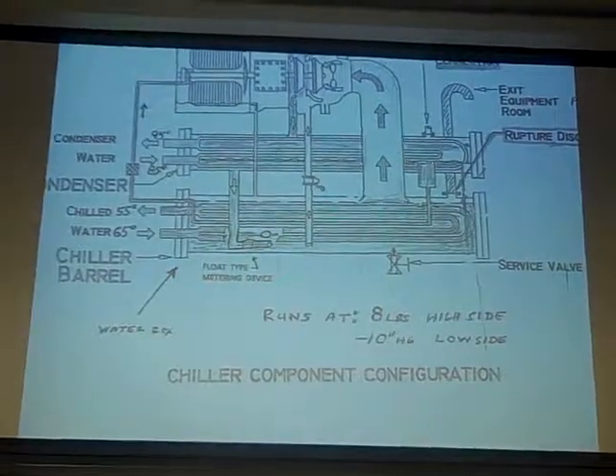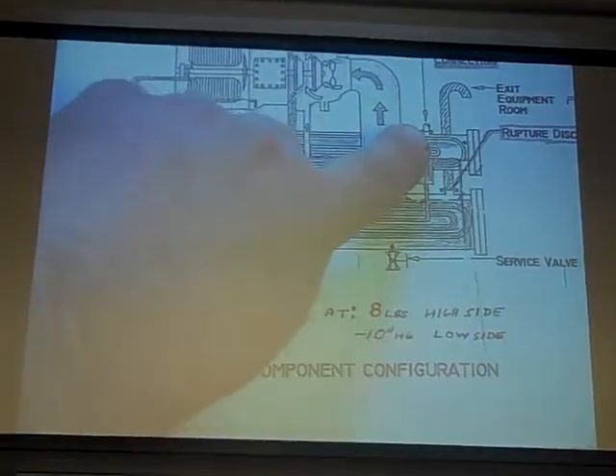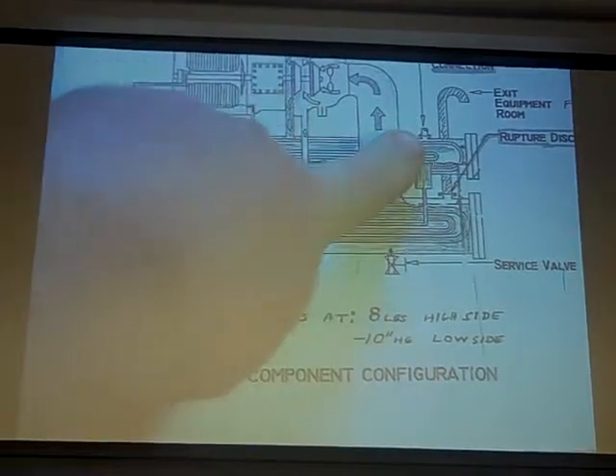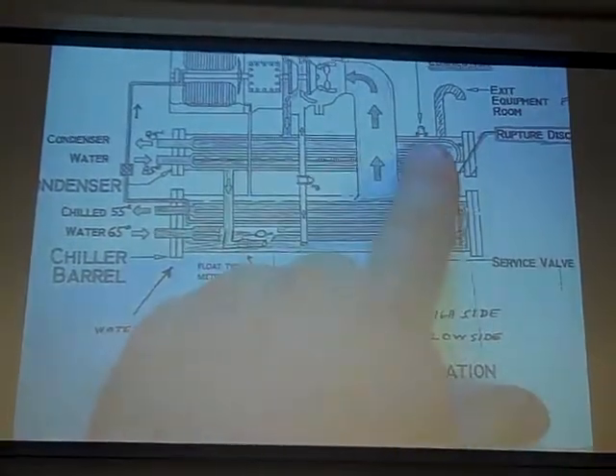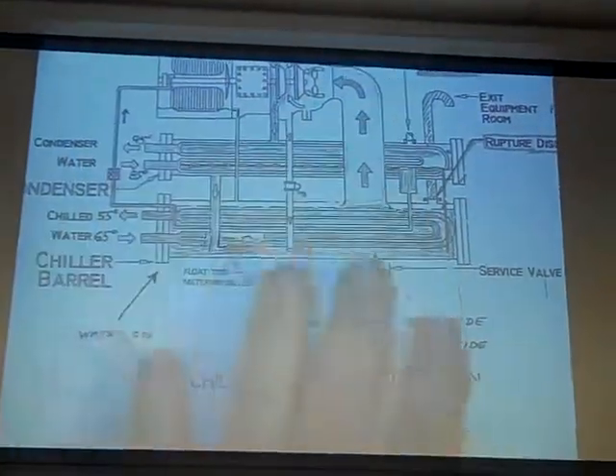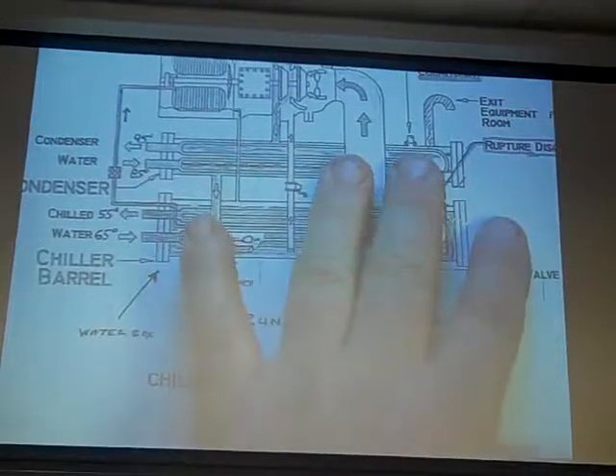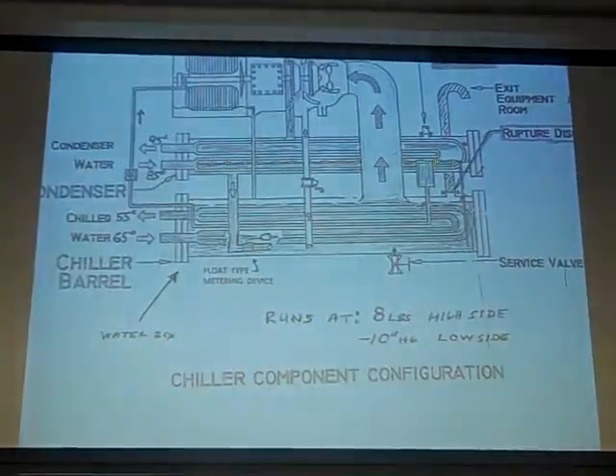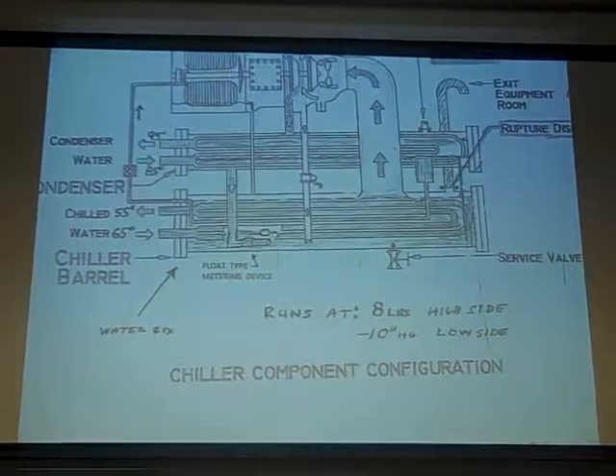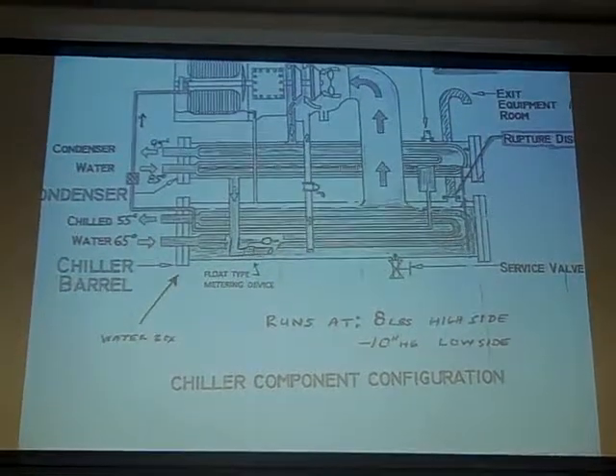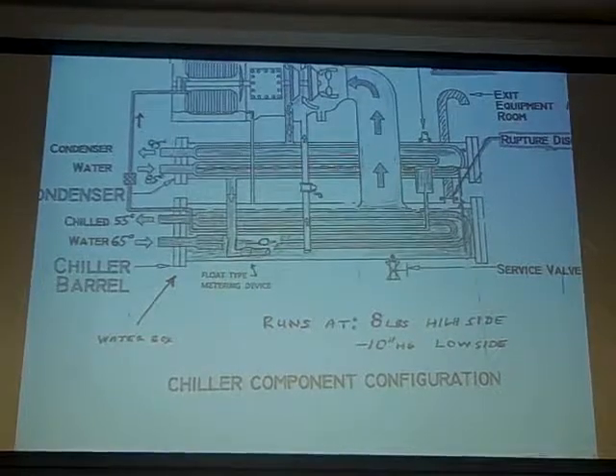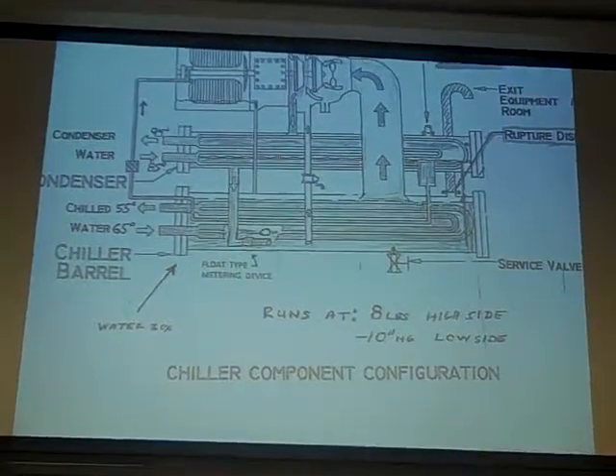And it's really, this little connection right here is where your purge unit would sit. They don't have a purge unit on here, but that's where the purge unit would connect to. It's the highest point in the system. Any non-condensables are going to migrate their way up to the top of the condenser, and the purge unit's just going to pump them off and get rid of it. Pretty much it for the chiller.